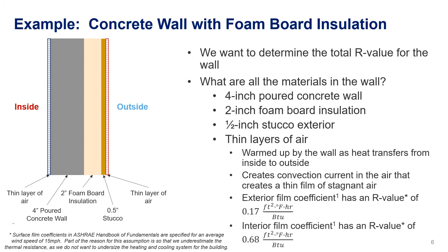Likewise, on the inside of the wall, we have the same thing, except in this case that inside layer will get colder than the indoor temperature and air tends to fall down. And again, it creates this kind of layer along the surface of the wall. Because we don't have the wind impact on the interior, that resistance is a little bit higher — it's 0.68, with the same units as the exterior film coefficient. We'll call this the interior surface film coefficient, or interior film coefficient for short.